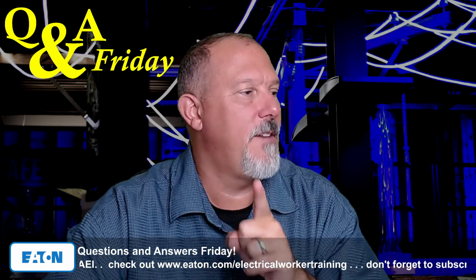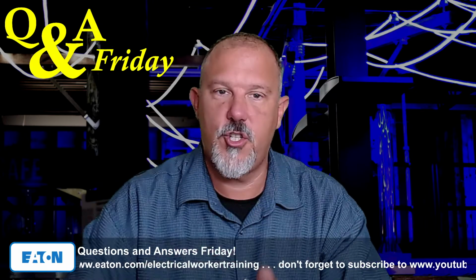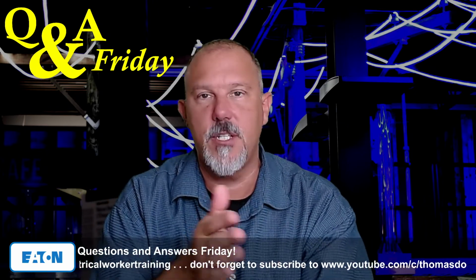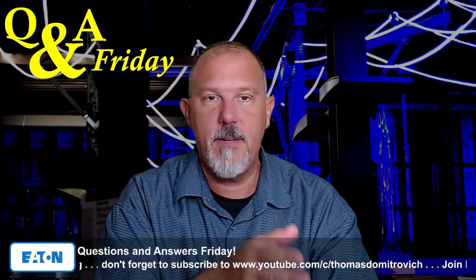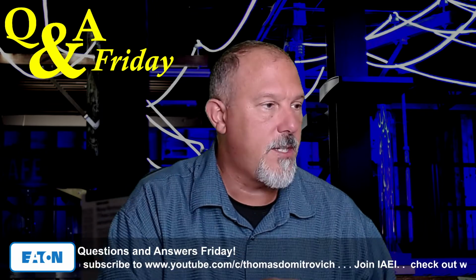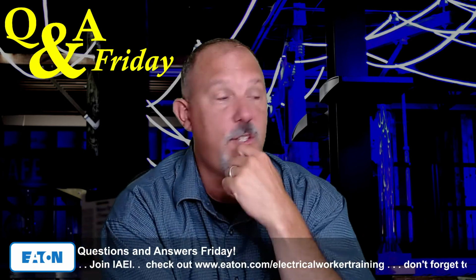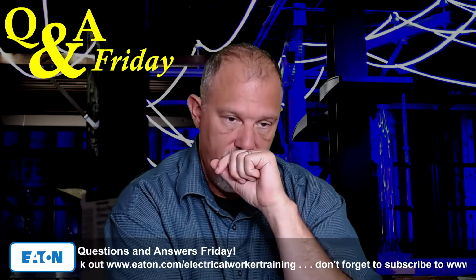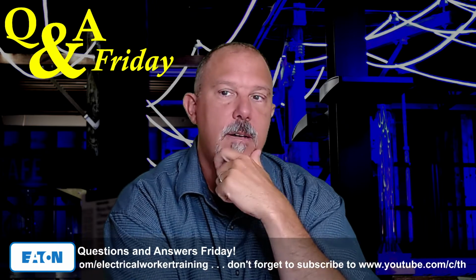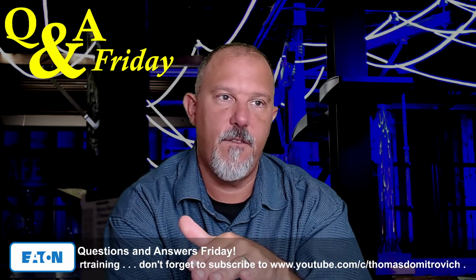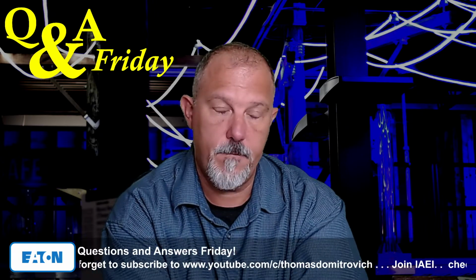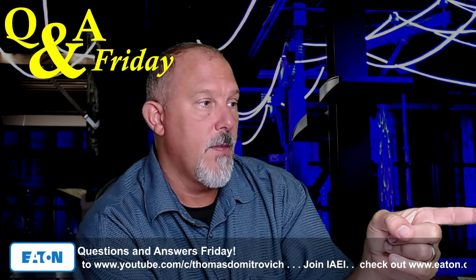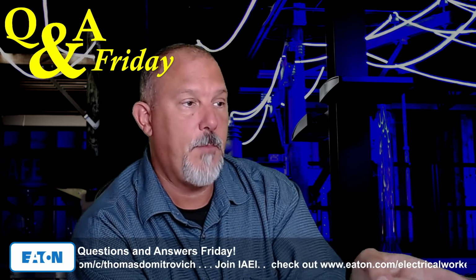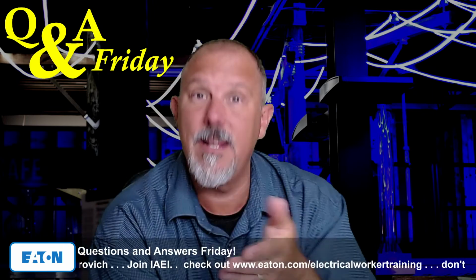All right, so I was in the middle of answering the one-to-one transformer question, which was on transformer applications and protection, and it was about assuming an infinite bus, about 500 MVA on the primary, connecting straight to the grid. How does a transformer limit fault current? And I would suggest, Navneet, that to understand what a transformer does for fault reduction, you made the statement that you know a transformer has impedance, but would that impedance be able to limit the fault current? And my answer to that would be yes.